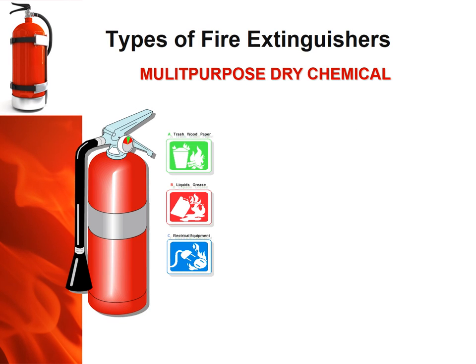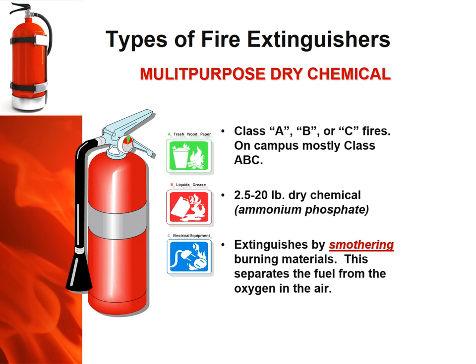The multipurpose dry chemical fire extinguisher is the one used most often at WC Striegel. It's class A, B, or C, available in 2.5 to 20 pound canisters of ammonium phosphate, pressurized between 50 and 200 psi by nitrogen gas. Smaller units last about 8 seconds; the larger 20 pound canisters last about 25 seconds of discharge time. It has a pressure gauge for visual inspection and a 5 to 20 foot maximum effective range. These extinguishers work by smothering burning materials, blanketing the fuel and separating it from oxygen.